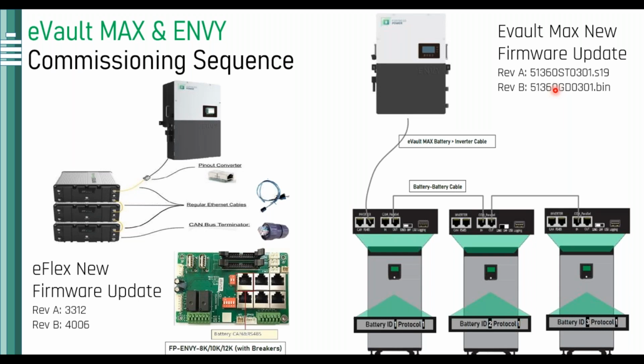So that said, to communicate various batteries, for instance, you have the eVault MAX, you have 3, right? The eVault MAX has a touch LCD where you can program what the battery ID is. So let's say you choose this as the master, right? So if this is the master, then this would be battery 1, this would be battery 2, and this would be battery 3. Okay, the protocol is always going to be one. Protocol means the communication protocol that you would use between our eVault MAX and the ENVY inverter.